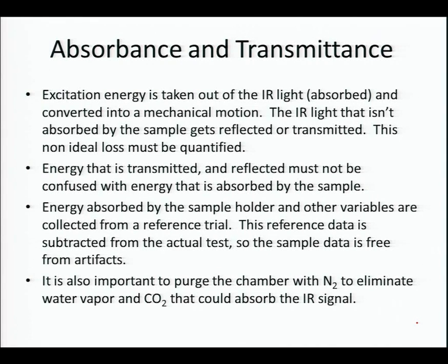Then you take a measurement, and you're going to measure the sample holder. The sample holder itself is going to absorb some of the infrared, so you save that data, place your sample in, and do the same procedure, eliminating carbon dioxide and water by putting a nitrogen purge in the system. Typically that's 10 or 15 minutes. Then you measure your sample on the sample holder, and at that point the computer is going to subtract the previously saved data of the sample holder, and then you're going to know what was absorbed by only the sample.